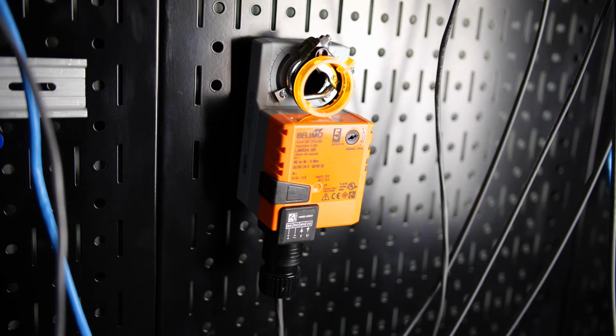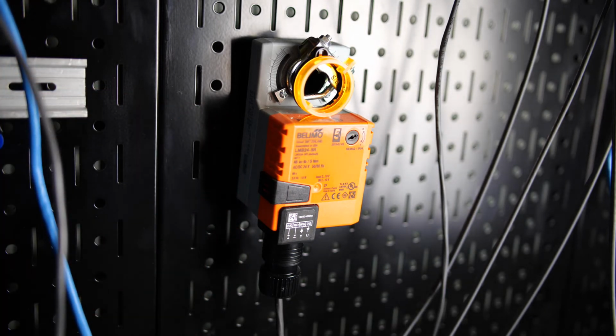Okay, as I was saying though, we can see right here, this is an actuator, and what it's going to do is take a 0 to 10 volt DC signal from our controller, and it is then going to cause the actuator to open and shut. So other things that we'll use an actuator for are dampers, where we want to connect to the damper and actually drive it open and closed. Valves, where we want to connect to the valve stem and drive it open and closed.